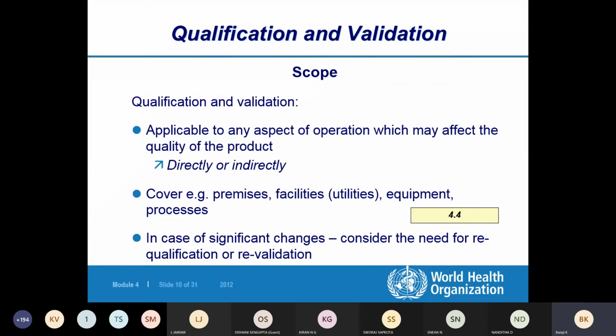validated. Suppose you want to use the autoclave at 135 degrees, but initially you have not used or validated it for 135 degrees, and now you are planning to use it for 135 degrees, then you have to prepare a protocol and submit that I'm going to do this 135 degree sterilization, so that I can check whether my autoclave is working fine at that high temperature for 3 minutes or 5 minutes, whatever your time interval may be. So this is the new requirement.